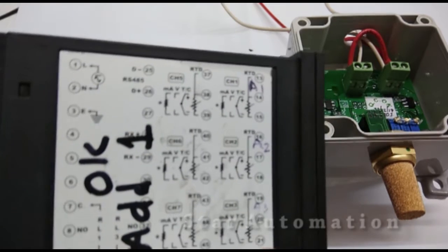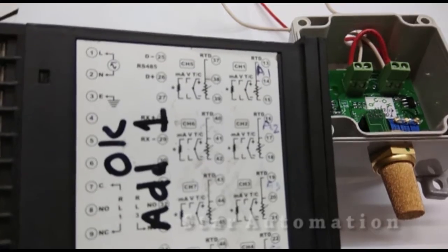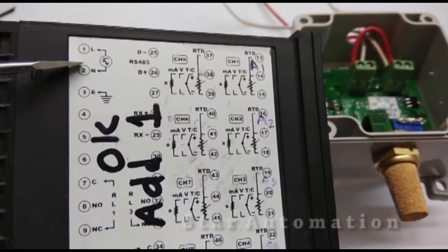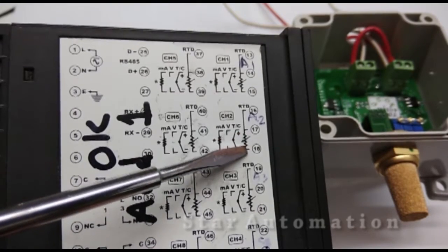Now we will use a scanner module to display this signal. This is an eight-channel universal scanner from Masibus. Looking at its connection diagram, terminals one and two are for line and neutral to power the module. This scanner accepts milliampere, volt, thermocouple, and RTD signals, but we will connect our 4 to 20 milliampere signal.